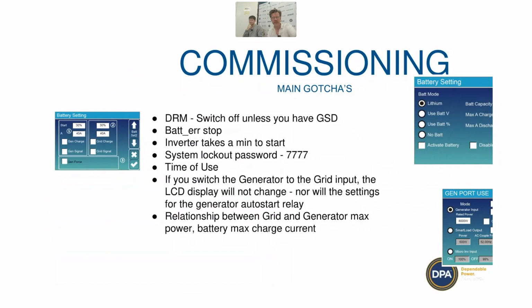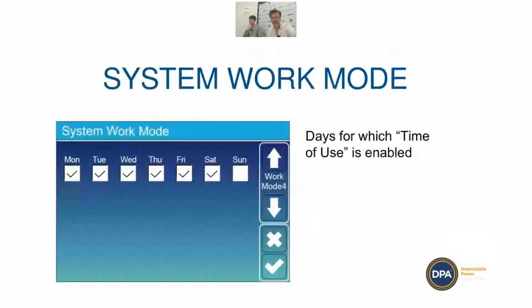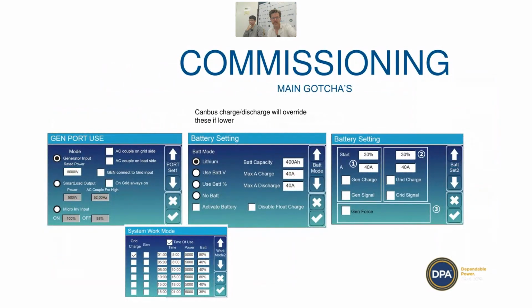So the main gotchas with commissioning it: DRM needs to be switched off when you first turn it on, and BMS error stop needs to be on. Take into account that the inverter takes a little bit of time to start whenever you make a change. You've got the system lockout password, and you've got to get your head around time of use. If you're doing it for the first time, give us a call and we'll help you with it. If you switch the generator to the grid input, well, I'll go over this in a moment with the generator port.